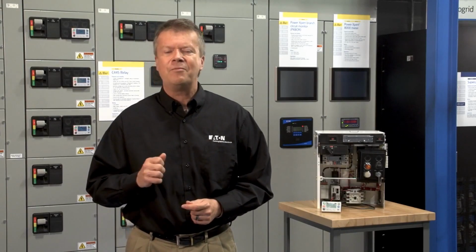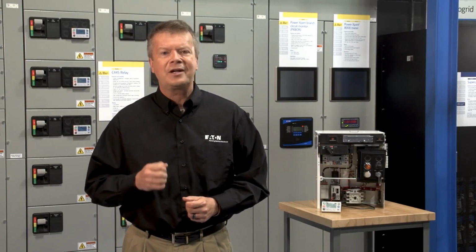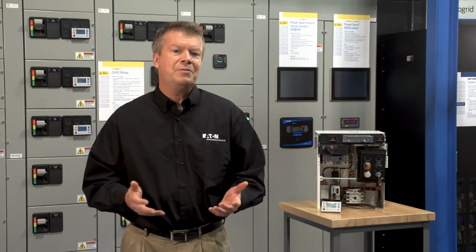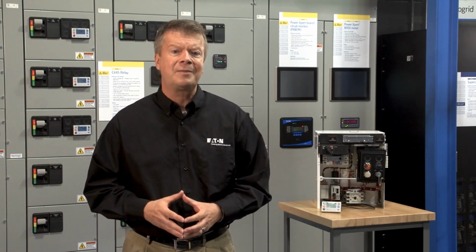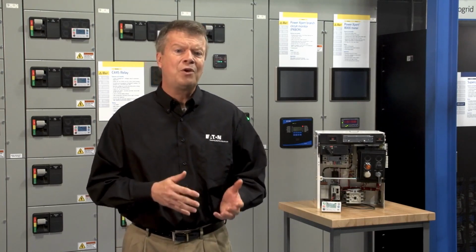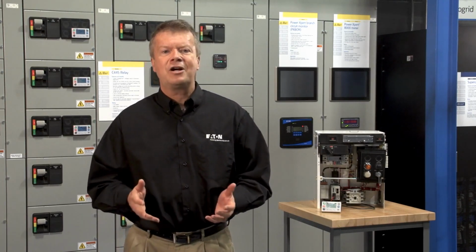Magnetically held contactors have a much longer life, but they do require continuous power being applied to the coil to stay closed. They might be rated for millions to perhaps 10 million mechanical operations. Magnetically held contactors have a problem if their coil voltage drops. This could be caused by a fault elsewhere in the system. Latch contactors solve this problem because they are mechanically held.